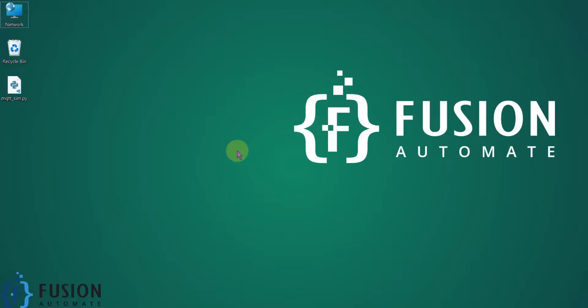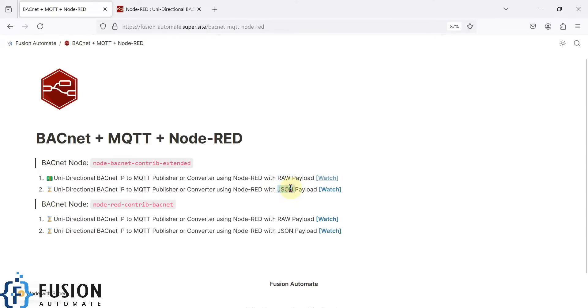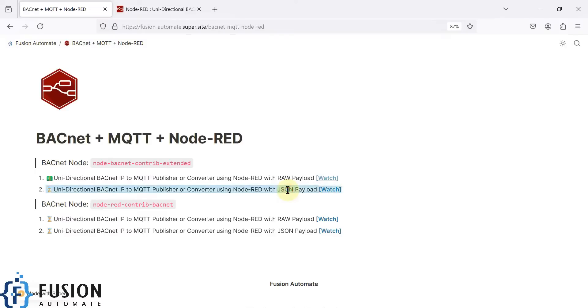Hi everyone, and welcome. In this video we will see uni-directional BACnet IP to MQTT publisher using Node-RED. We are going to publish our BACnet IP device data to an MQTT broker in the JSON payload format. Previously we covered a video explaining how to publish BACnet IP device data to an MQTT broker with raw payload. Now we will cover JSON payloads. The difference is that with raw payload, each topic contains only one value, whereas with JSON payload, one topic can contain multiple values.